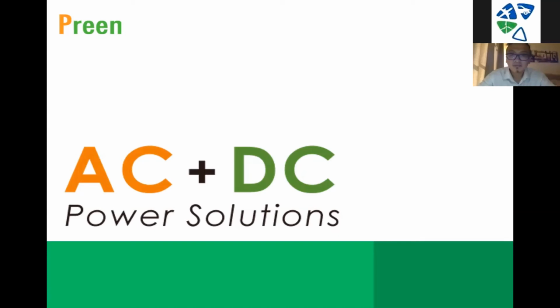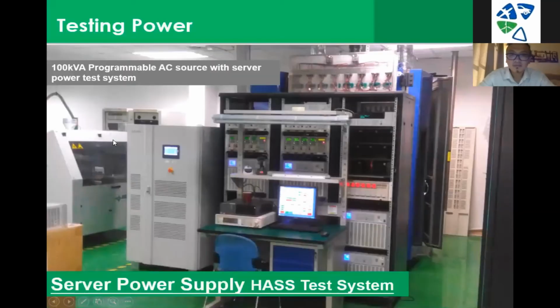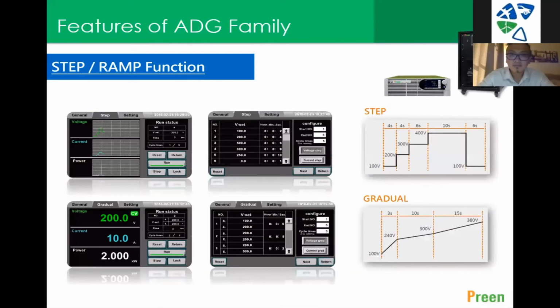Oh, DC power supply, okay good. So for DC power supply, you can set it up as CC mode. Let me show you a little bit. So here you can set up CC mode, because in CC mode you can set different current limits. So when the current hits the limit, it will hold the current constant, like 2 amp, and jump to 5 amp. You can do different cycling testing, so like 2 amp here, 5 amp here, 2 amp here, 5 amp here. You can set up different profiles for that. Does that answer your question?